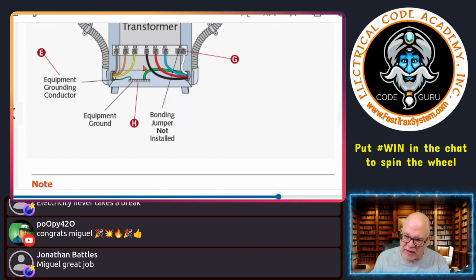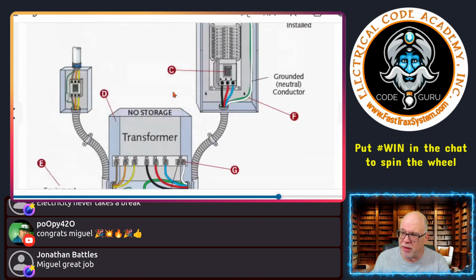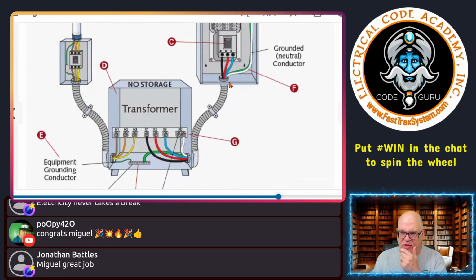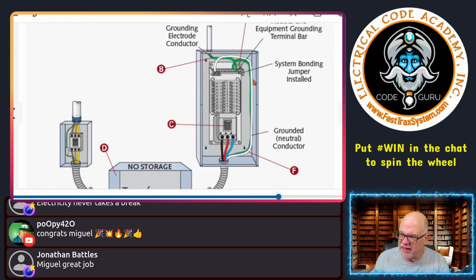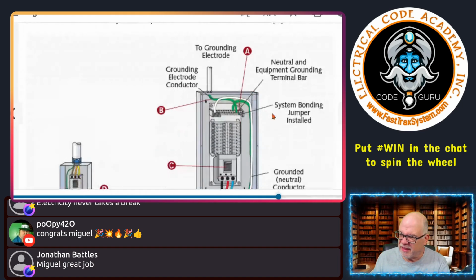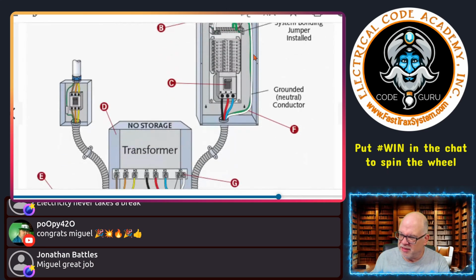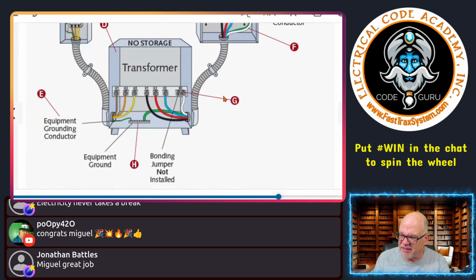They'll put the system bonding jumper in it. Just make sure you don't do both, because in this case you see it's a metallic path and you're going to cause problems. And you see right here that there is a conductor running through right here. Okay, so this is your system bonding jumper right here. And you see this conductor running through right here, running all the way through.